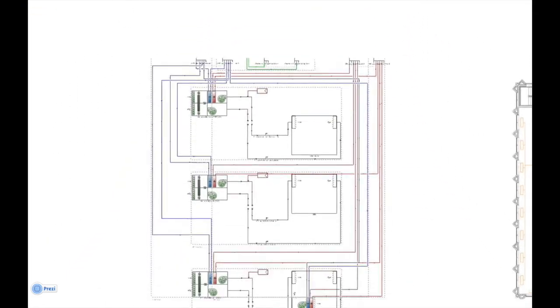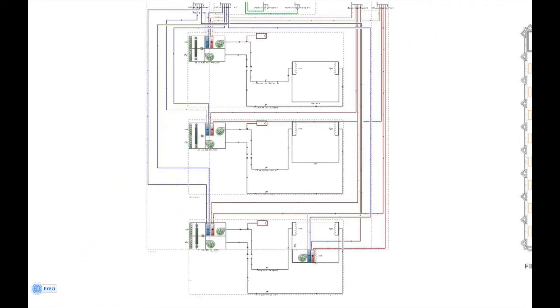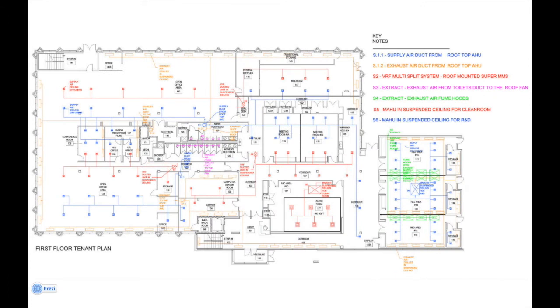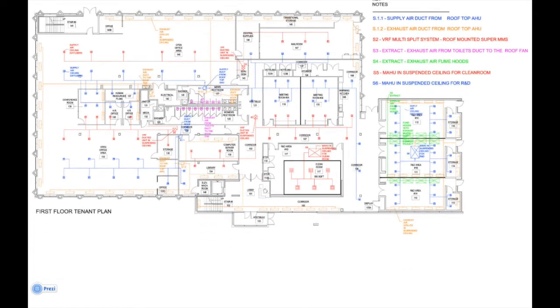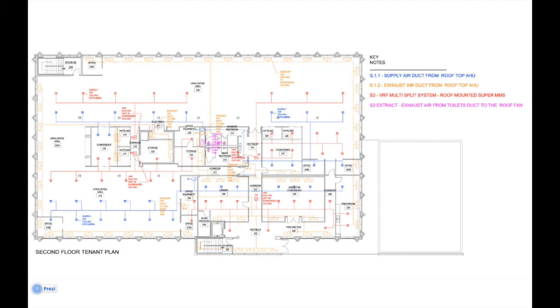The exhaust rooftop fan is designed for air extraction from toilets and restrooms. Here we see air handling units and fan coil system schematic, version 1. Version 2. 3 air handling units with heat recovery, gas-fired condensing boiler, chiller, exhaust fan for toilets and rest areas. Multi-split VRF system, air source heat pump for basic heat loads in summer conditions are considered. For clean room and R&D department, modular packaged ceiling-mounted air handling units are designed. These preliminary design drawings for first and second floor are shown.